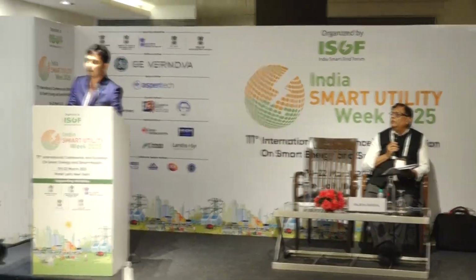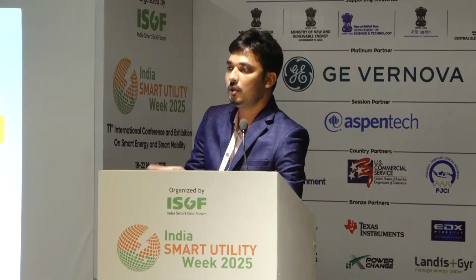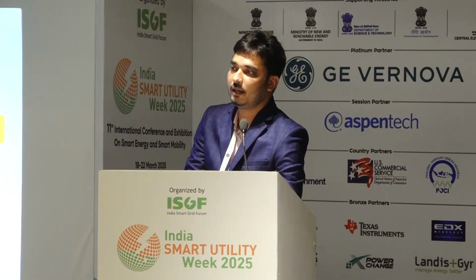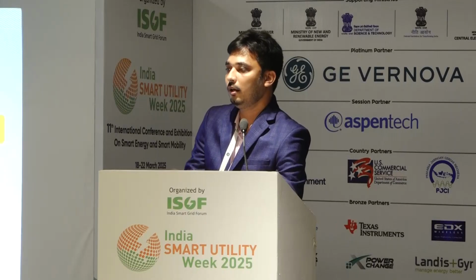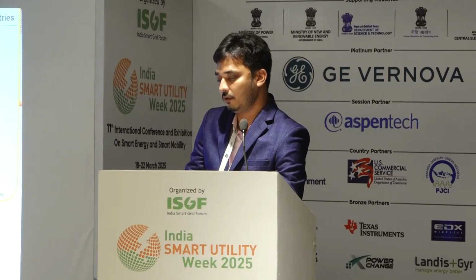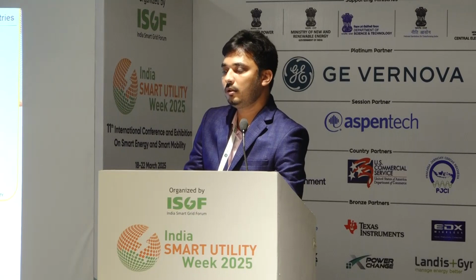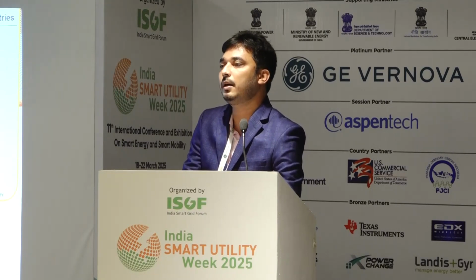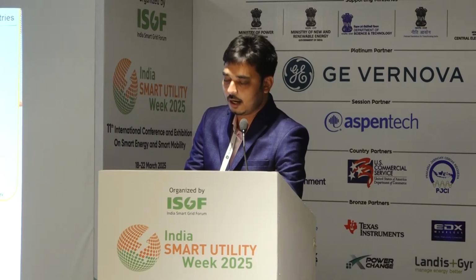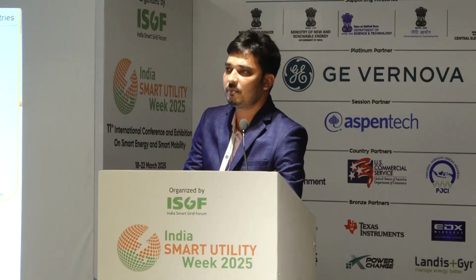Let me simplify: will this battery-based system work only for microgrid, or will it work at the regional level? It can work in other grids, but we have tested it for microgrid purposes, because in a microgrid there is less inertia. We use inertia control to enhance the inertia, because in alternating energy systems using an alternator, such as thermal power plants and hydropower plants, there is already high inertia. There is no need for inertia control there.